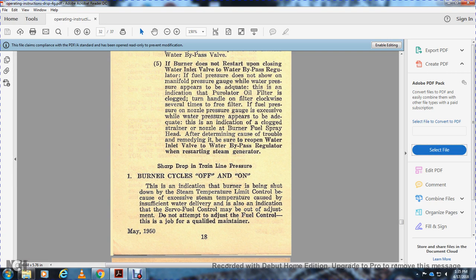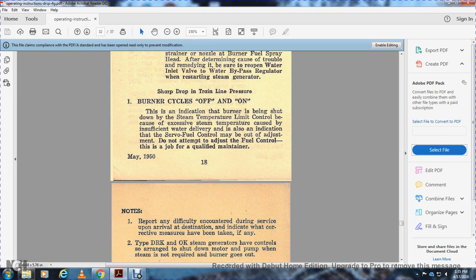A sharp drop in the train line pressure with the burning cycle going off and on indicates the burner is being shut off by the steam temperature control because of excessive steam temperature cutoff from insufficient water delivery. It is also an indication that the servo fuel control may be out of adjustment. Do not attempt to adjust the fuel control. This job is for a qualified maintainer.